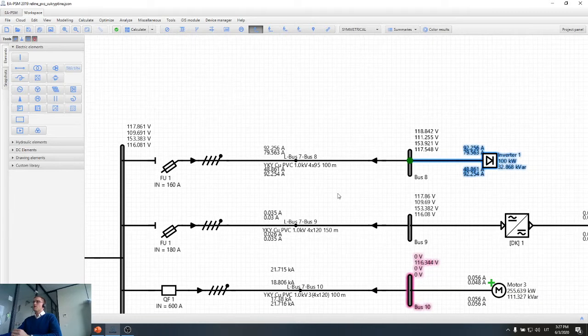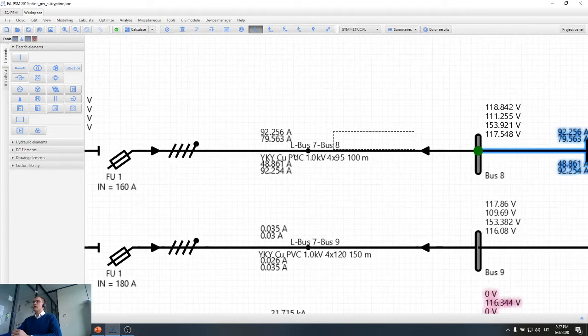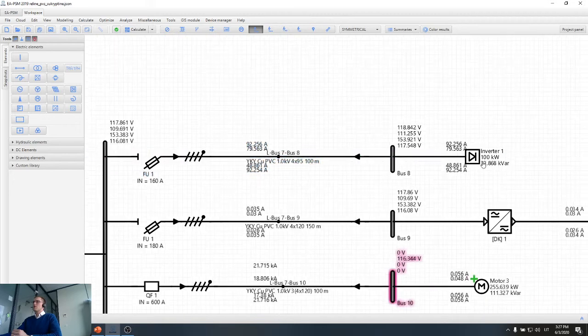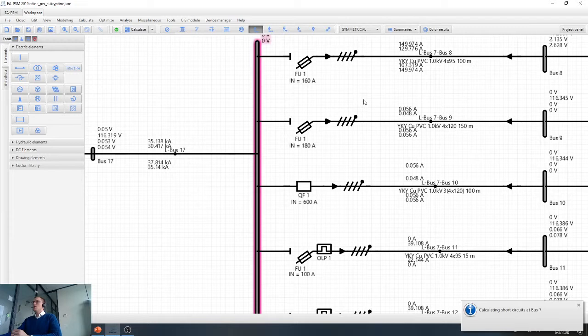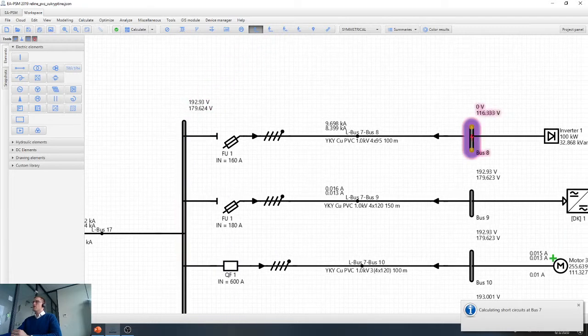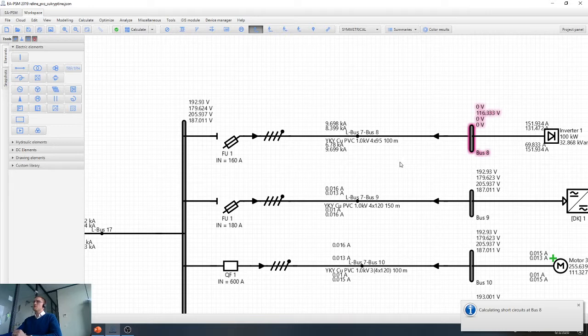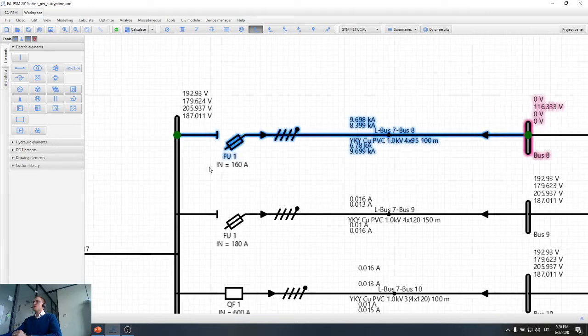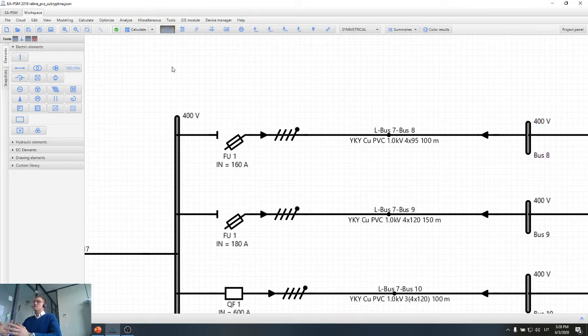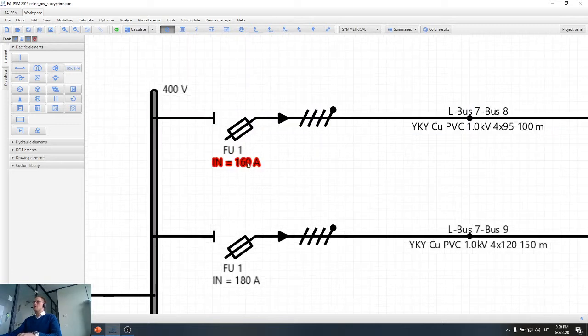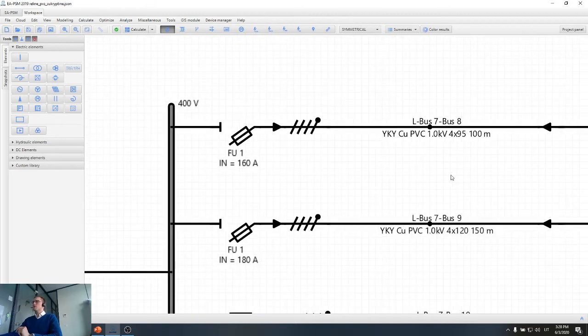So all we need for the inverter protection is to protect the cable which connects the inverter with the main bus bar. If we have a short circuit at the end of the cable, we should have some protection device which will quickly disconnect that short circuit. The least expensive device for protection coordination is a fuse, and you can see that I already have a fuse selected here. Its nominal current is 160 amps. So how did I select the current for the fuse?